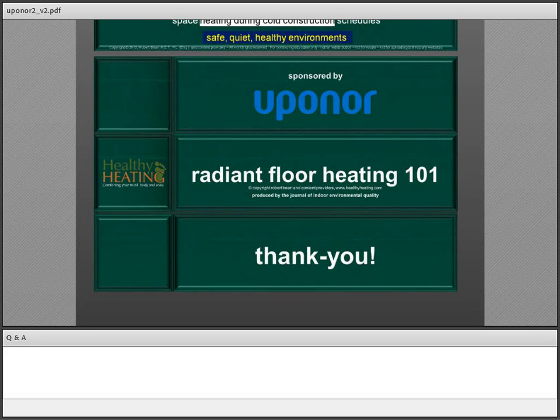That particular product is an electrical-based system, not gas, so it lends itself really well to photovoltaics or anywhere hydropower is used. As designers, it's important to match source energy with load energy in terms of exergy. I'm a huge fan of electrical devices, heat pumps, or an electrical boiler, when that electricity is generated with PV, wind, or hydro. But if we have to generate high temperatures for power generation with an electric boiler or heat pump, keep in mind we're using something like 3,400 degrees Fahrenheit for a 90-degree use, so it's not a real ideal match. So to answer this question, first, it is electric.